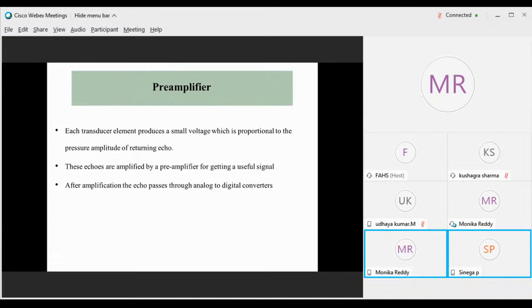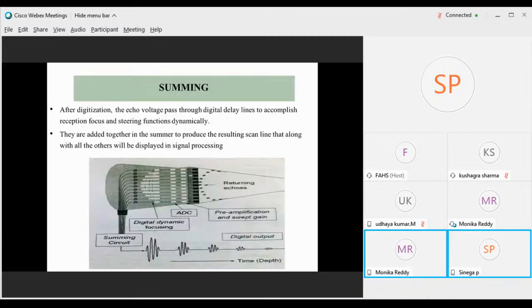So the pre-amplifier. Each transducer element provides a small voltage which is proportional to the pressure amplitude of the returning echo. So these echoes are amplified by a pre-amplifier before going to the receiver. After amplification, the echo passes through analog to digital converters. So this will boost the echo signals. And then the summing: after digitization, the echo voltage passes through digital delay lines. So this will receive the returning echoes at the proper time and then add them together in the summer to produce the resulting scan lines that can be displayed along with the others. Even the first reached beam will be stored there, kept there until the last beam reaches the transducer, and then it will process the signal and display together.